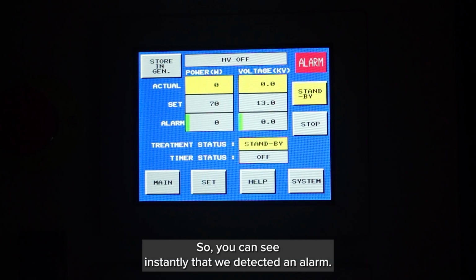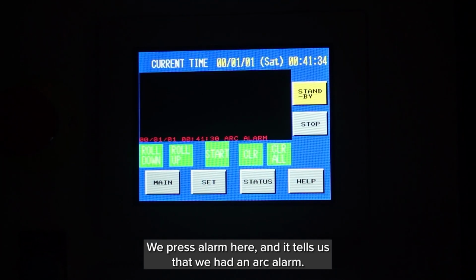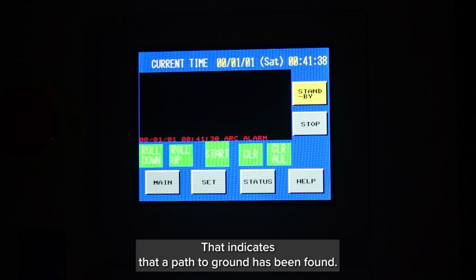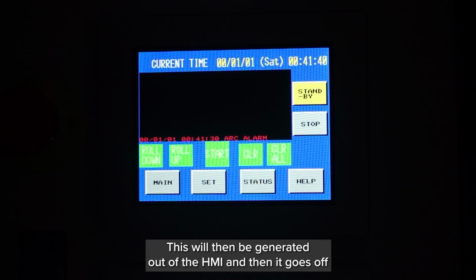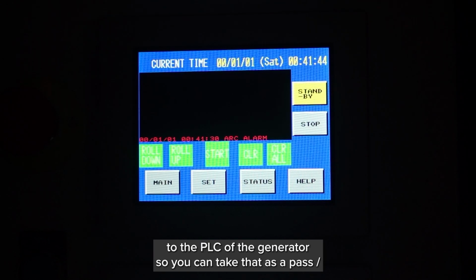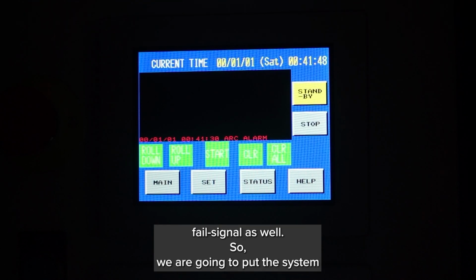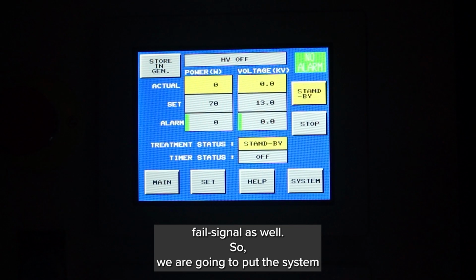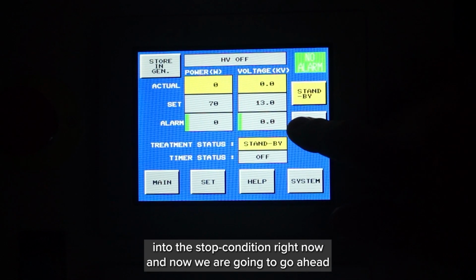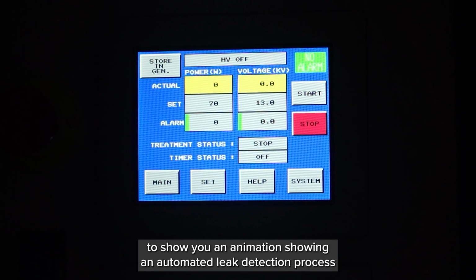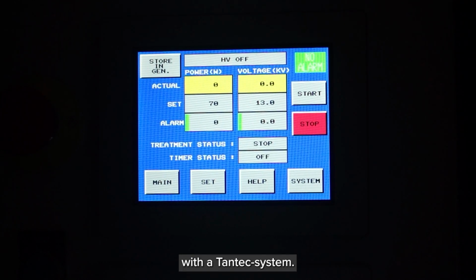So you can see instantly we detected an alarm. We press alarm here, and it tells us we have an arc alarm. That indicates that a path to ground has been found. This would then be generated out of the HMI, then goes off to the PLC of the generator, so you can take that as a pass-fail signal as well. So we're going to go ahead and put the system into stop condition right now. And now we're going to show you an animation showing an automated leak detection process with the Tantec system.